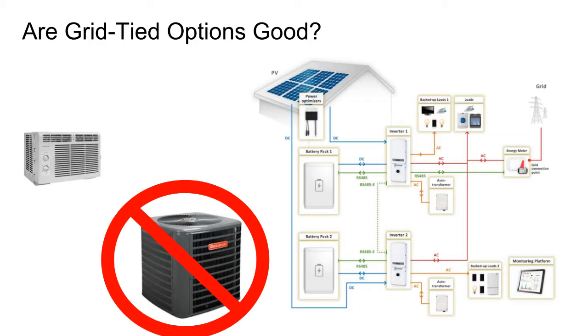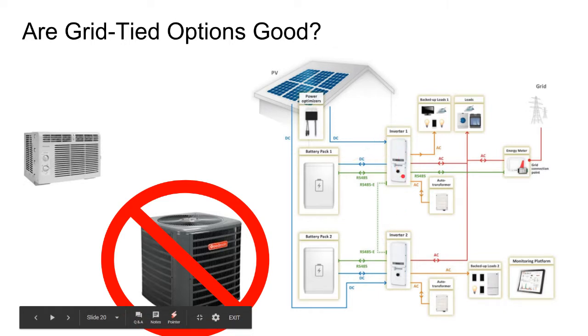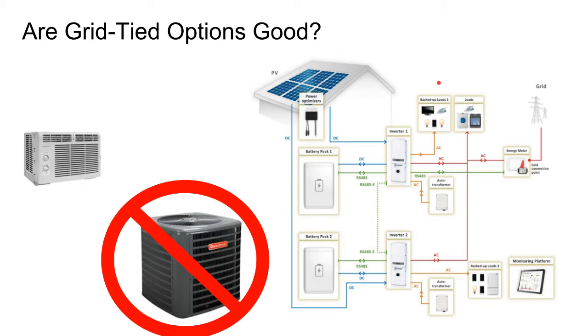You go and you look at what they power, and they say, okay, well, you have a grid-tied inverter that can outflow and sell back to the grid, and you have your electric service panel with all your loads on it, and then you have your inverter, and what we're going to do is wire a critical load panel to it. And we're going to rewire your electric service panel, and any critical loads we're going to put on to your backup. And your battery is going to supply the backup.